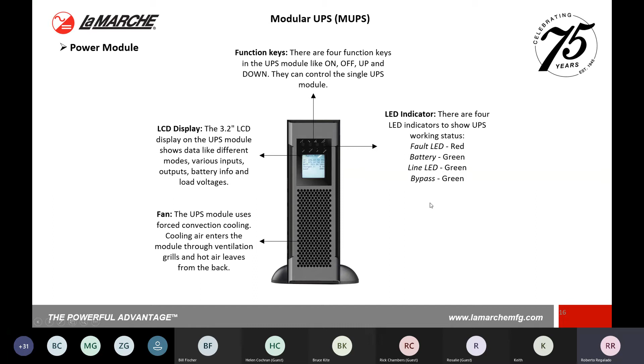As for the operation of the MUPS, in the standard operation mode you have a couple of options. You have your standby mode, where your load is not yet powered off of your actual inverter. You have your line mode, battery mode, bypass mode, eco mode, and shutdown mode. There are different reasons that you would want one or the other. Obviously, if you want to have it going through your bypass all the time, or going through your inverter the whole time, running off your battery, since we do have a static bypass switch integrated into the system, you can definitely designate which one you want to do.